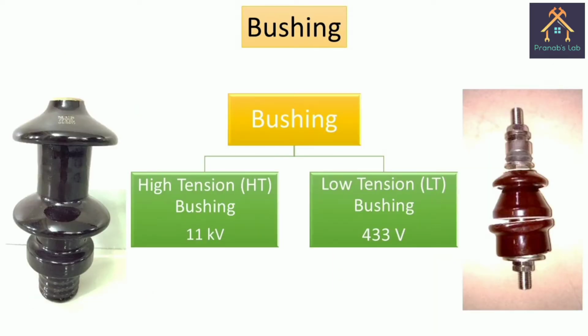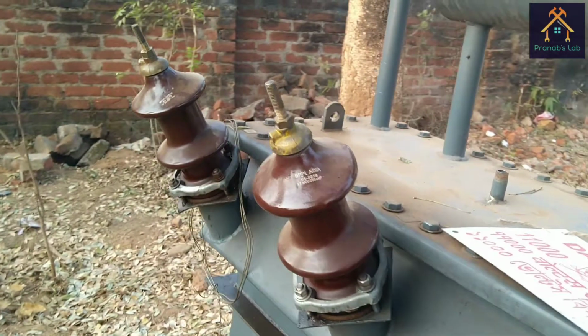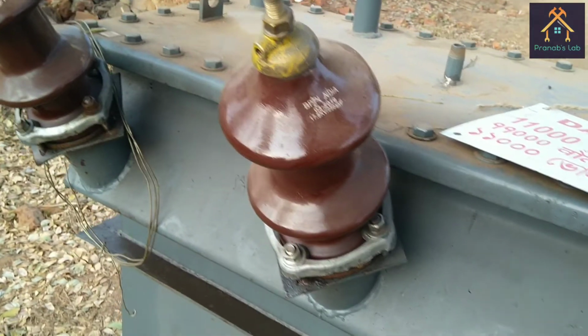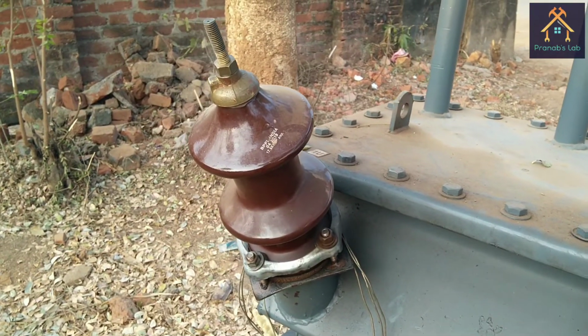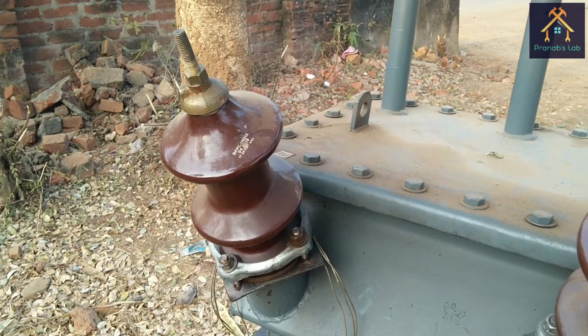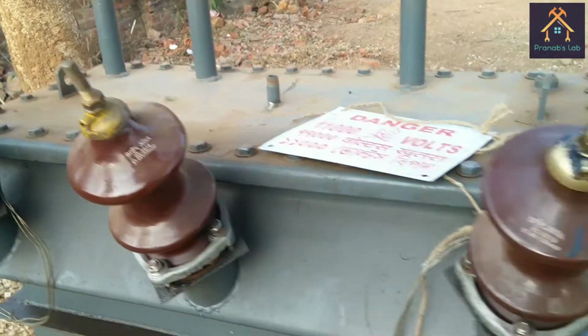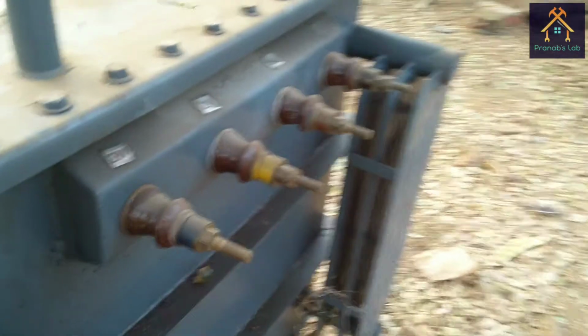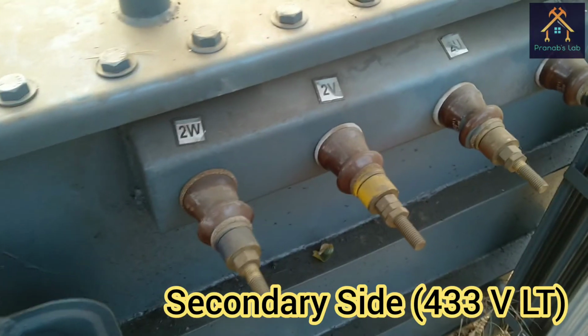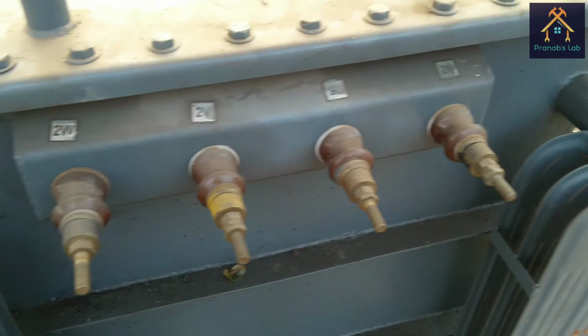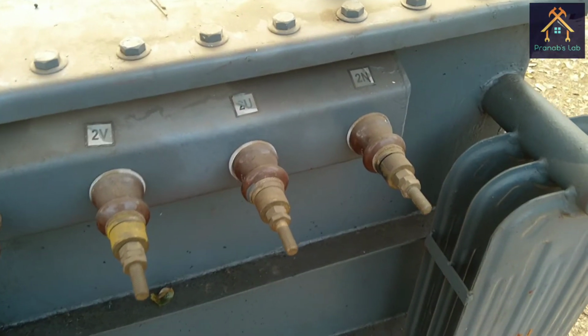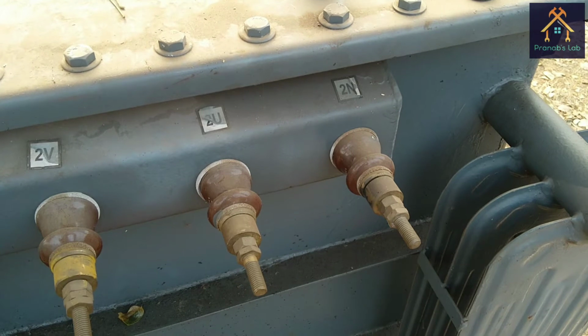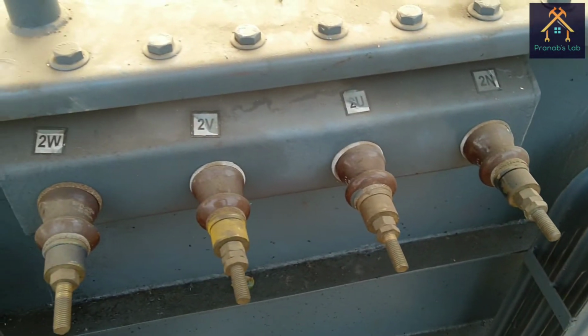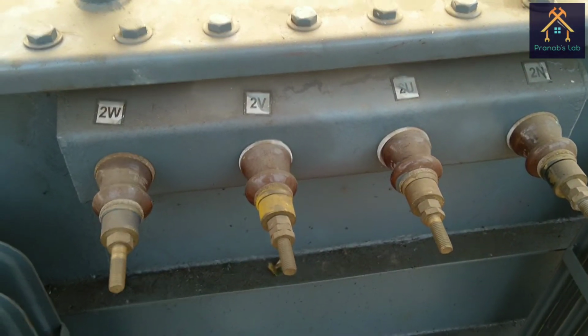There are two types of bushing used, that is high tension bushing and low tension bushing. You can see these are the three phase high tension bushings, and red, yellow, blue colors are painted on them for phase marking, and these are made from porcelain. These are the 433 volt low tension bushings having 3 phase with neutral terminals. The terminals are marked as 2U, 2V, 2W and 2N.